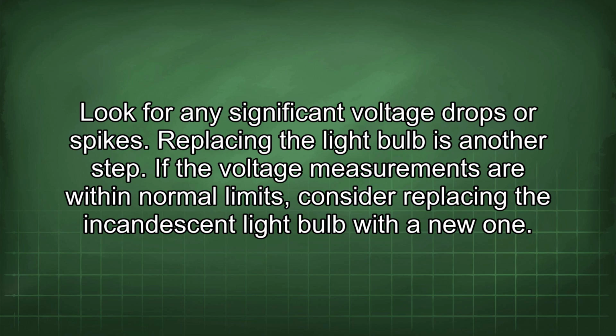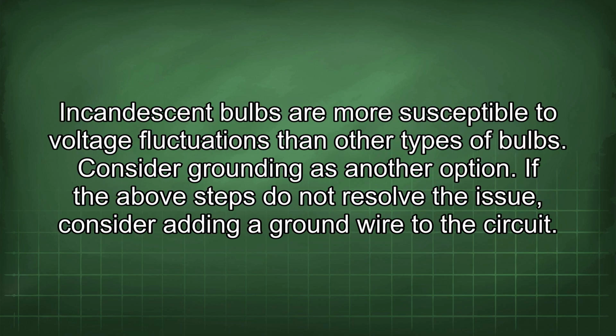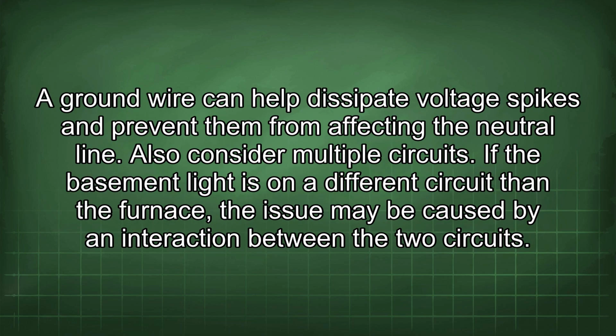Replacing the light bulb is another step. If the voltage measurements are within normal limits, consider replacing the incandescent light bulb with a new one. Incandescent bulbs are more susceptible to voltage fluctuations than other types of bulbs. Consider grounding as another option. If the above steps do not resolve the issue, consider adding a ground wire to the circuit. A ground wire can help dissipate voltage spikes and prevent them from affecting the neutral line.